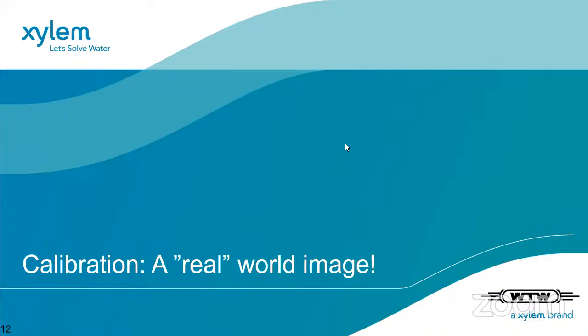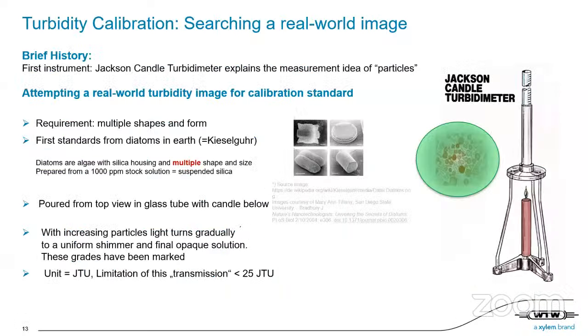So the next step, if we want to measure, we have to choose an optic. If we are in drinking water, we're going to choose the standard regulation drinking water. But then we have calibration. And the calibration is not easy because, let's say, people were looking for a long time for the correct calibration option. What we want is a calibration standard which gives us different formats, different sizes, and unevenly shaped particles, and that they can be dissolved in a solution.